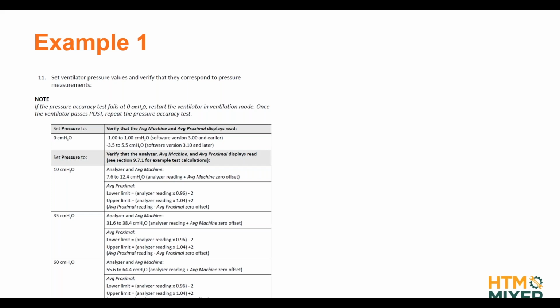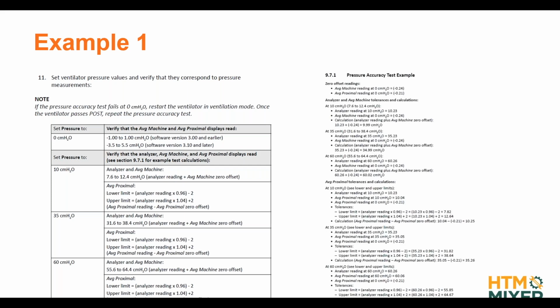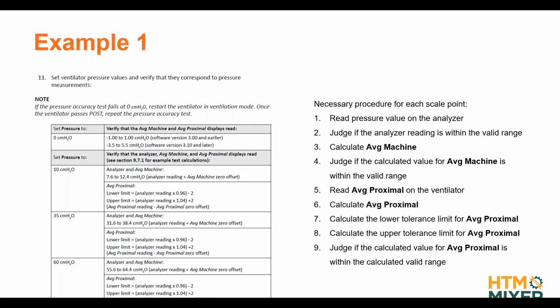We need to read some values, and then we need to set our ventilator to 10 centimeters of water, and then the challenge starts. We need to take some measurements, and then we need to do some calculations. We even need to calculate our lower limit and our upper limit, and we need to do that for each of the different scale points. So this ventilator manufacturer realized that this is quite complicated, so they added an appendix with a calculation example. I have detailed it for you. Per scale point, you need to go through 9 different steps of reading values on your analyzer and your ventilator, then calculate the valid ranges based on these readings, and then finally judge whether or not your calculated values are within the calculated range, right? So of course it's important that you are trained on the ventilators you are testing, but procedures like these can make it very cumbersome and prone to errors, right?